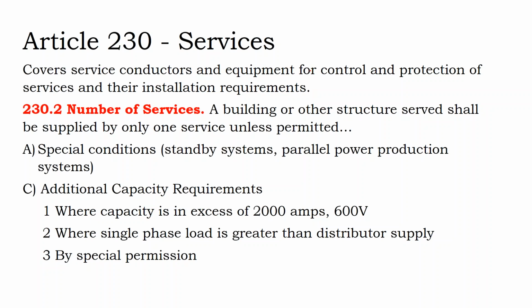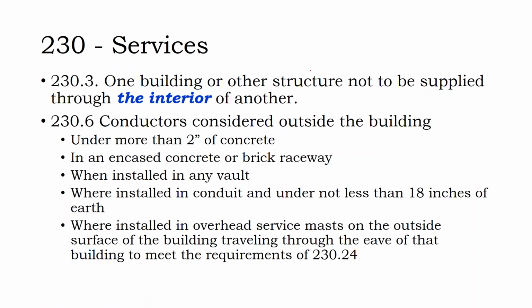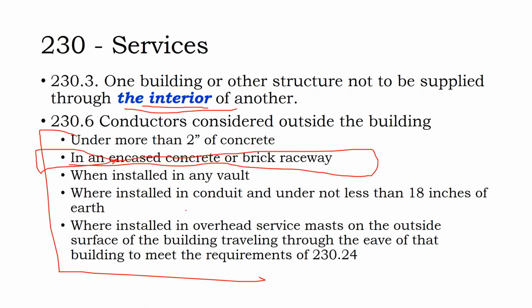So we talked about number of services. Generally, you try to supply one service to the building until you get into higher power draws, but you also have standby systems, solar arrays, on-site power. You're not supposed to supply one building through the interior of another building, and so the question is, what's considered the interior of a building? Basically, if you put enough dirt between two buildings, if you encase your wires in concrete, that's considered not being inside the building.